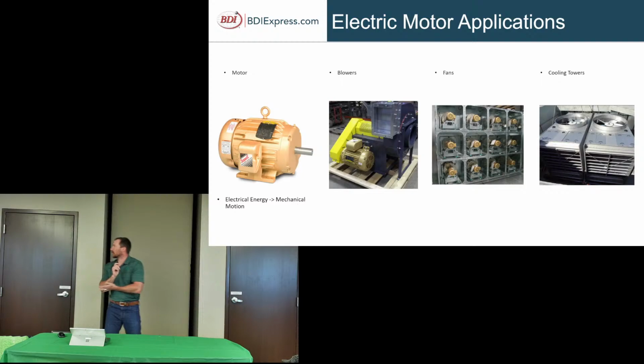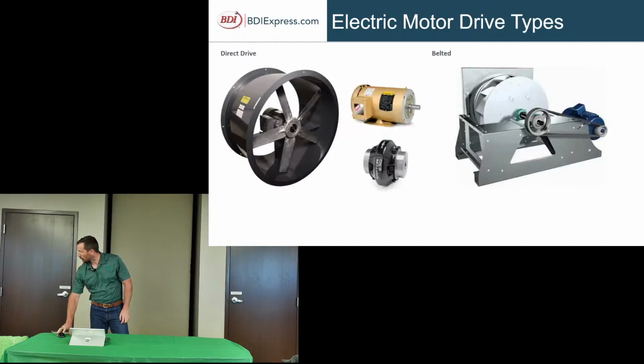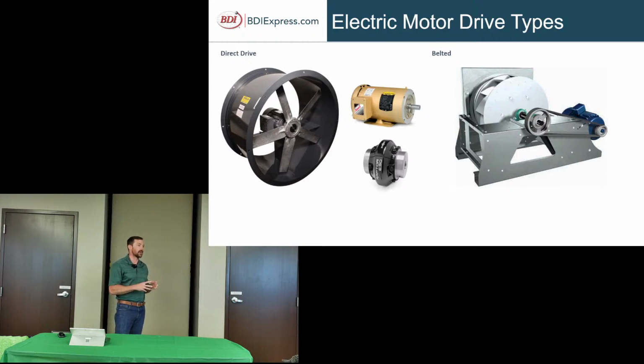So first, starting with motors. These Gold Baldor motors you guys probably see all over the place. There's other motor manufacturers, WEG, Toshiba, but WEG or Baldor is a very common one that we all see on air handling units, blowers, cooling towers. And then there's two types that are driven. I'm starting to see some directly driven fans, when the motor is coupled directly to the fan itself with a coupling, of which there are 10, 15 different styles. And then you have your belt driven, which is what Tim from Timken just went over.